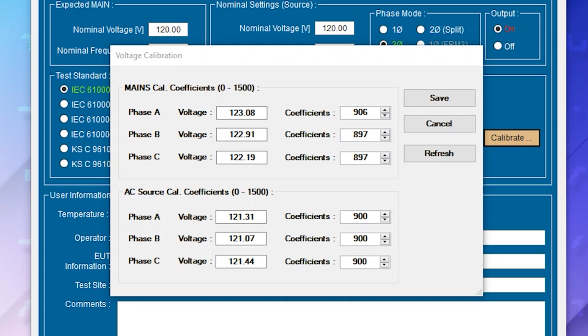We can do the same process with the AC source. However, typically the values shouldn't require much adjustment. Let's take a look right now at our phase A. We're measuring roughly 123.5 volts on our multimeter. So we're going to need to adjust the value of the coefficient so it reflects 123.5, or as close as we can get by selecting the up or down arrows. So let's go ahead and make that adjustment now.